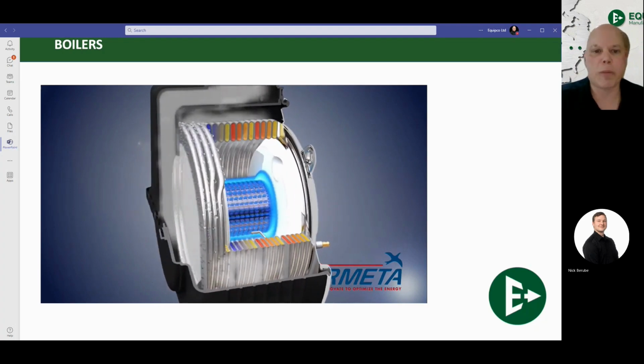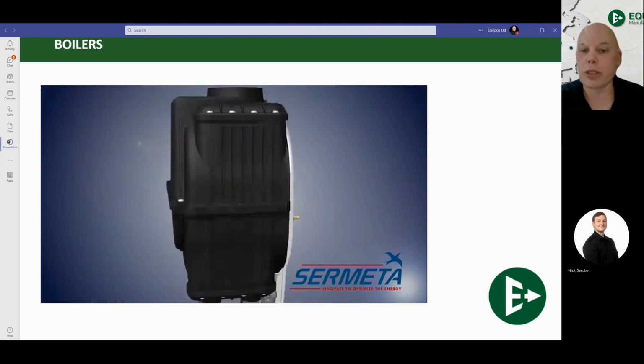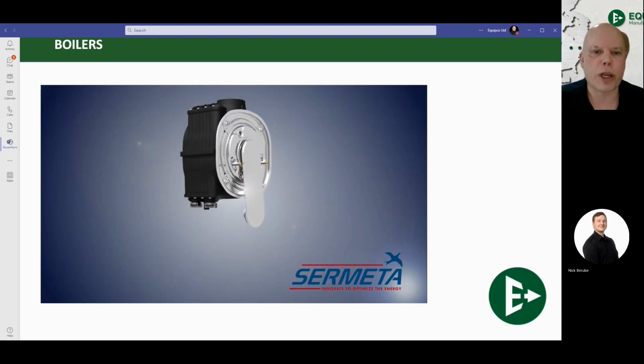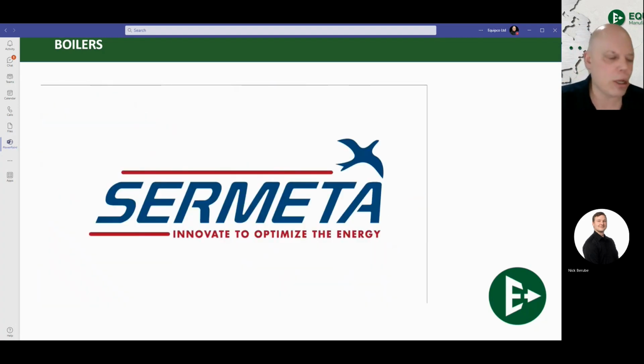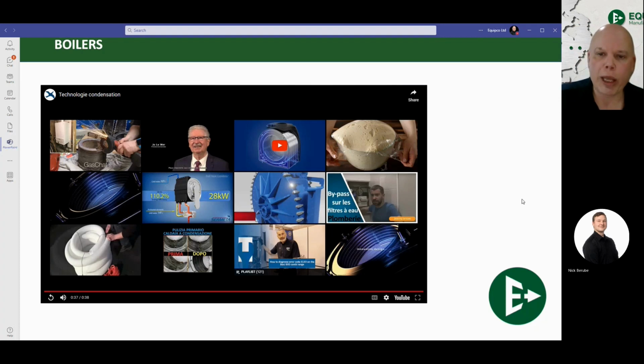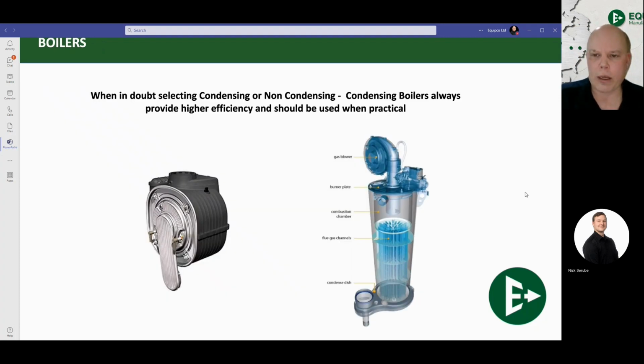So cleaning is going to take a little bit more time, but it does a really good job of heat transfer. They each have their pros and their cons. Fire tube: extremely low head loss, but a little bit more difficult to clean. Water tube: higher head loss, might require a couple extra components, but very easy to clean and very fast and quick to take apart. We're not here to pass judgment on either. These are just the main two that you're going to see in the vast majority of all the quality boiler makers out there right now.